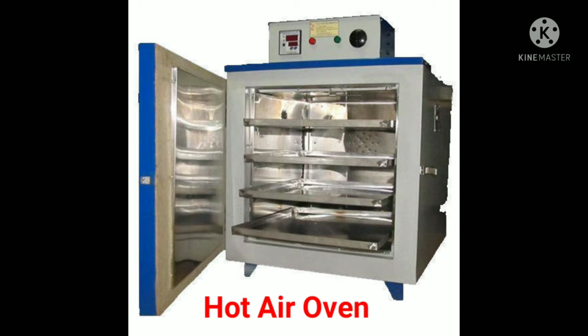This is the hot air oven where the items are sterilized at 160 to 170 degrees centigrade for 2 to 3 hours. Microbial death apparently results from the oxidation of cell constituents and denaturation of proteins.